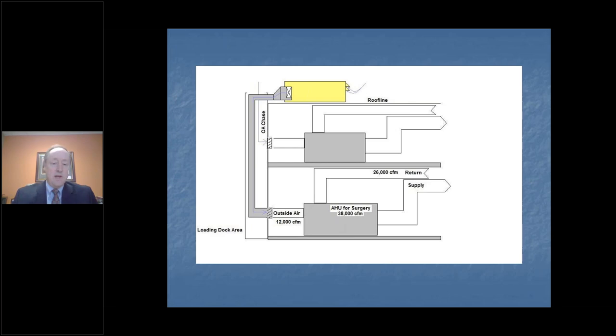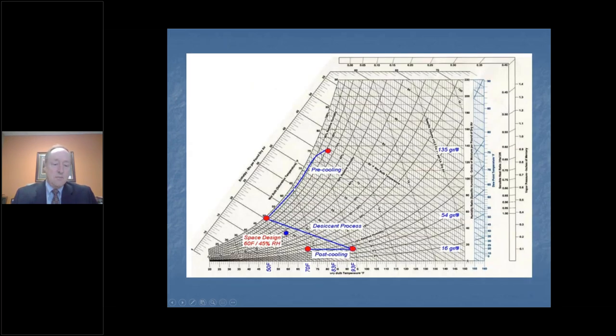This is the way we calculated and sized that up. We did pre-cooling all the way down to 50 degree dew point, and then we ran that through the desiccant rotor, and then we did some post-cooling to this particular condition right here, and then let the air handler mix this air with the return air to get to this point right here.